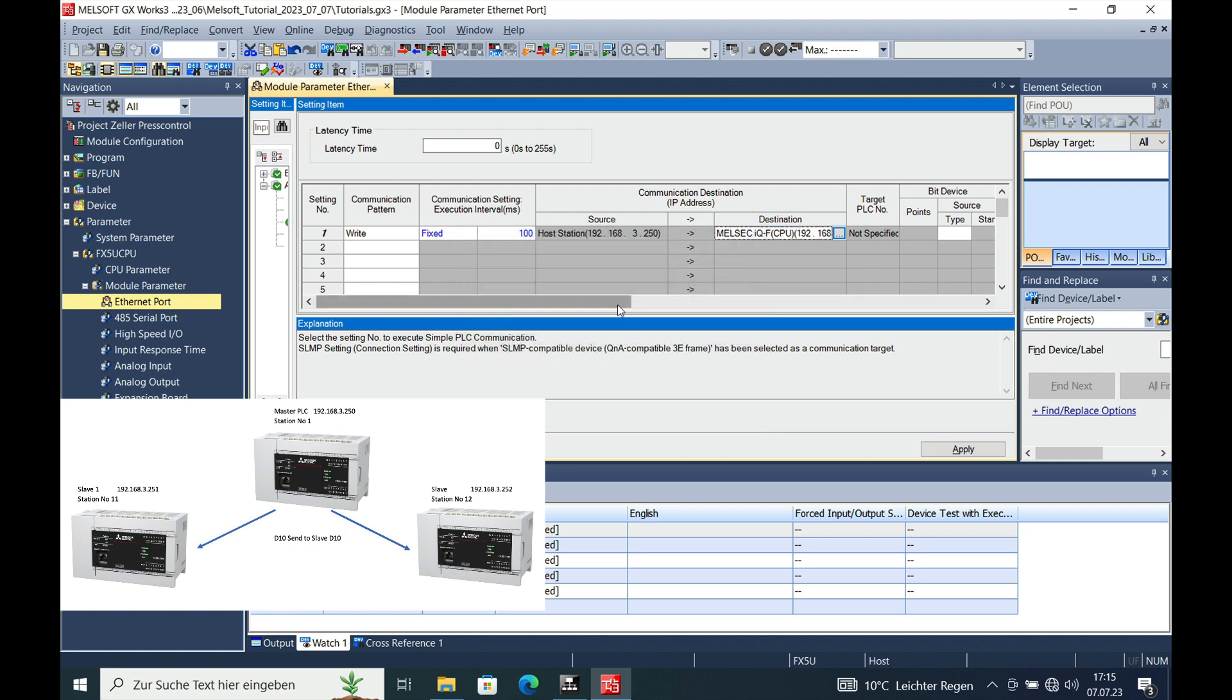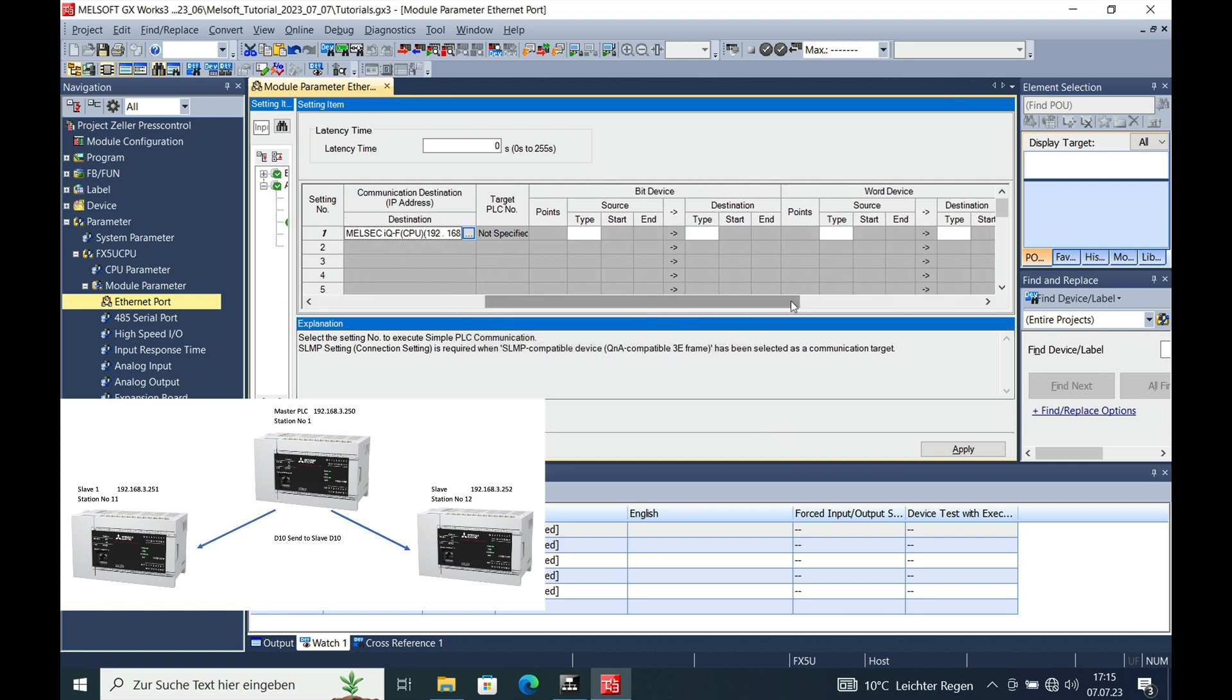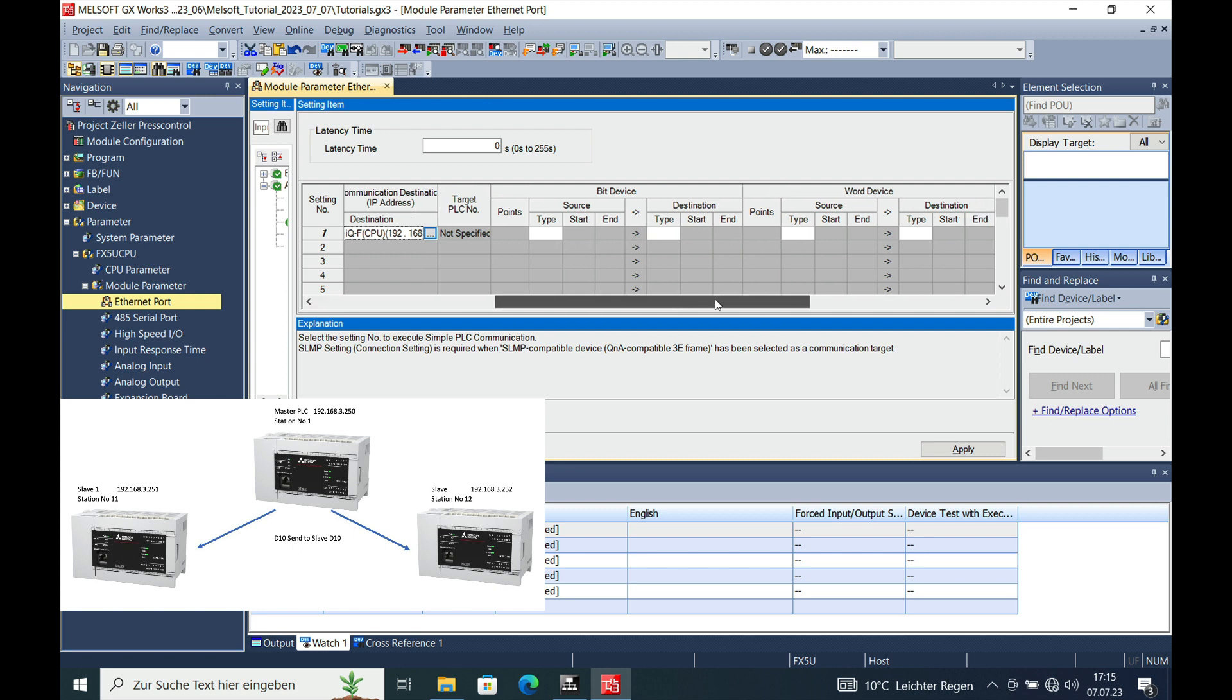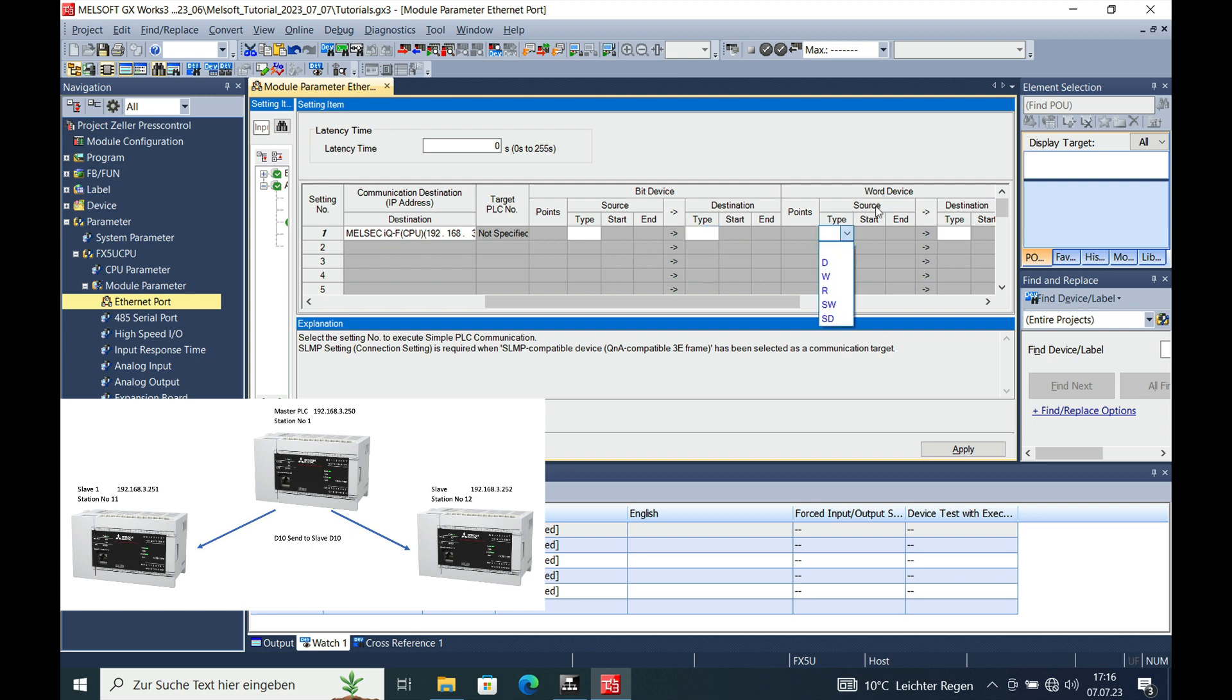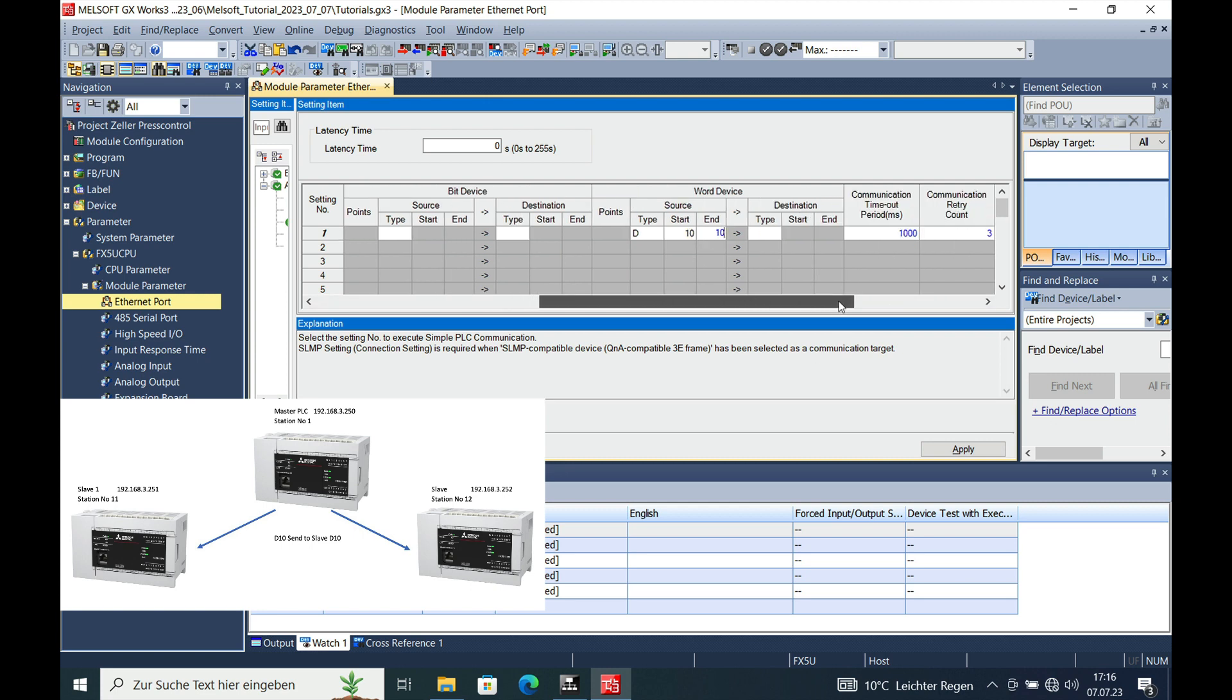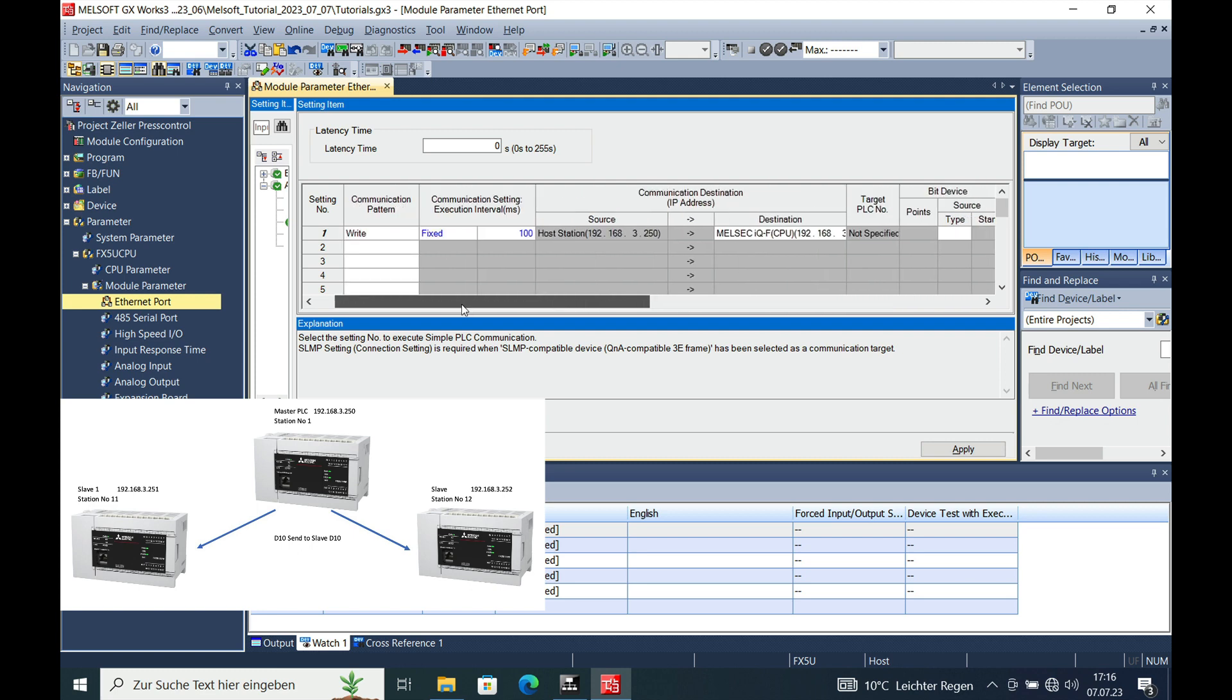The next step will be that we can choose on which device we want to transfer. I will skip the bit device because I don't think this makes much sense. So what I'm going to do is move the D10. The source on here D10 and the end also 10, we make it only one word. And the destination, that will be the slave number one, also starting with the D10, and automatically it puts in at the end the D10.